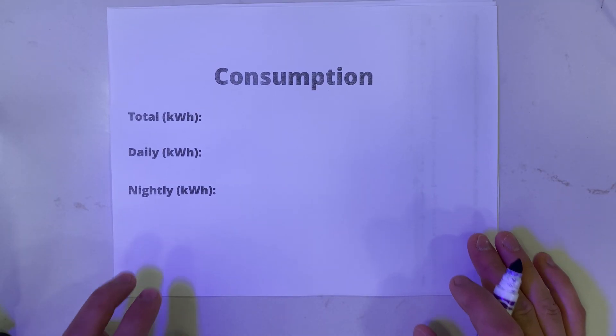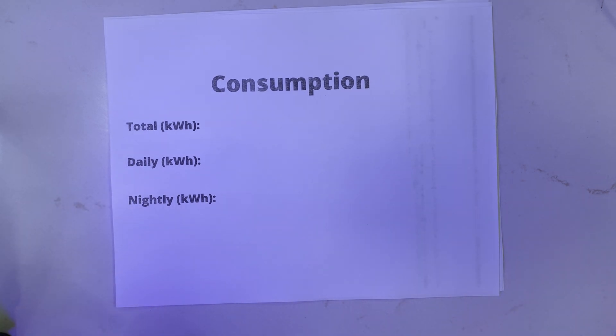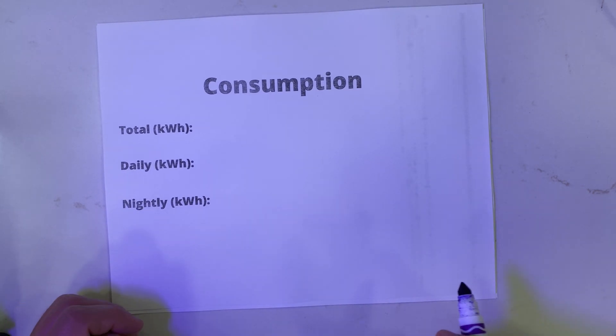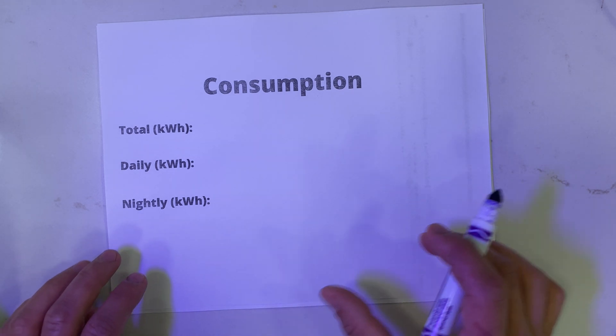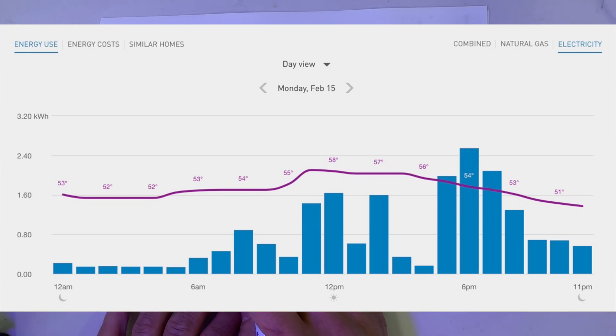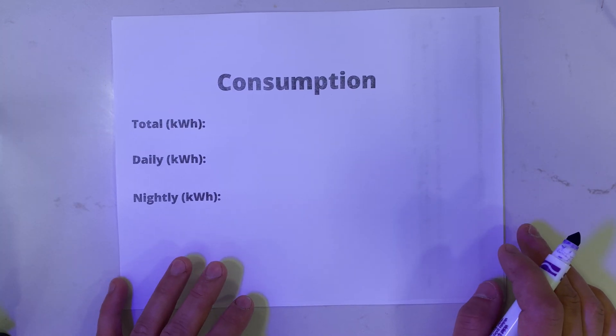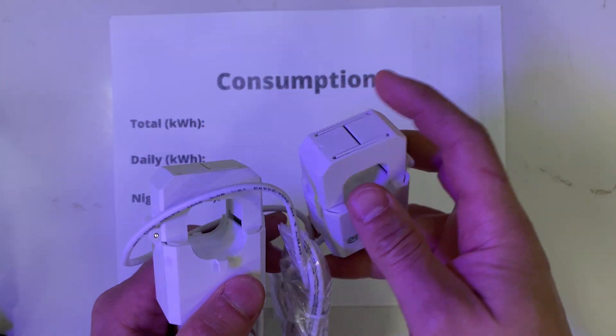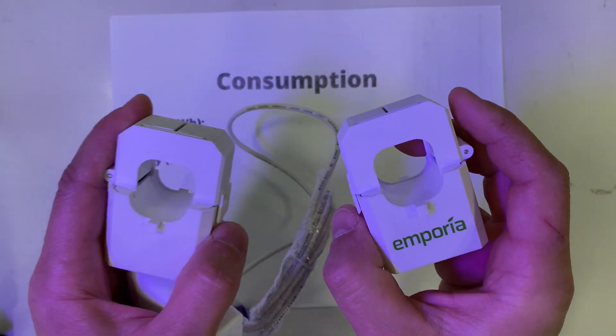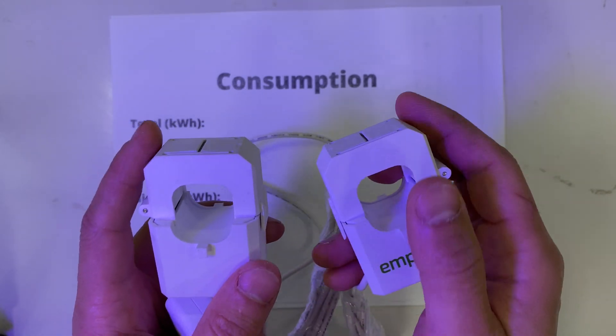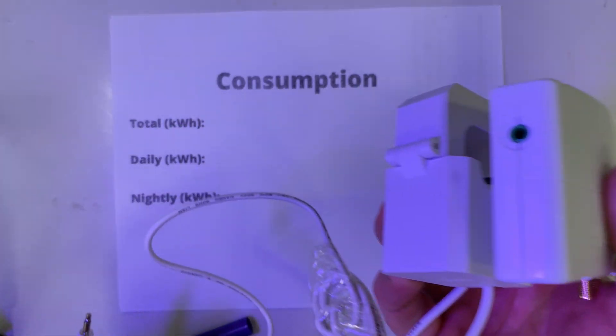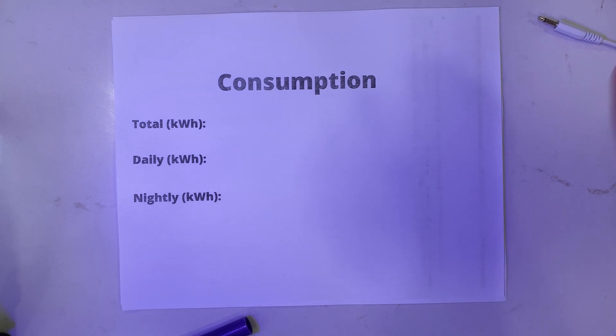The second piece of data we need is consumption. There are a few ways to get this. The first way is to go to your utility provider if you have grid power and check your daily usage — here's a screenshot from my provider showing kilowatt hours used every hour throughout the day. The second way is to get an energy monitor: you install CT sensors on the two main input wires in your electrical panel, and it tracks kilowatt hours going to your house in detail.